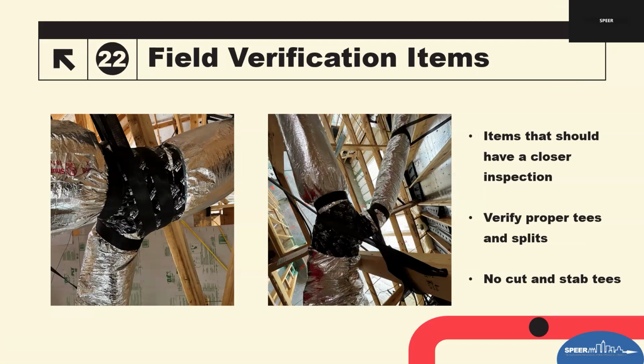Here they've basically crushed all of the outer insulation all the way around it by securing the tape. I understand the tape's 181. It's approved, but you're crushing all the insulation. That's a point of, basically not air, but temperature and heat fluctuations inside the ductwork will happen right there. If not, probably also condensation will happen right there. If you take a stick and lift up on it, realize there's no metal in it, that's because they just cut and stab without a fitting. That should not be allowed. It should be properly fitted with T's or splitters or Y's and then properly sealed and not just cut off to the side.